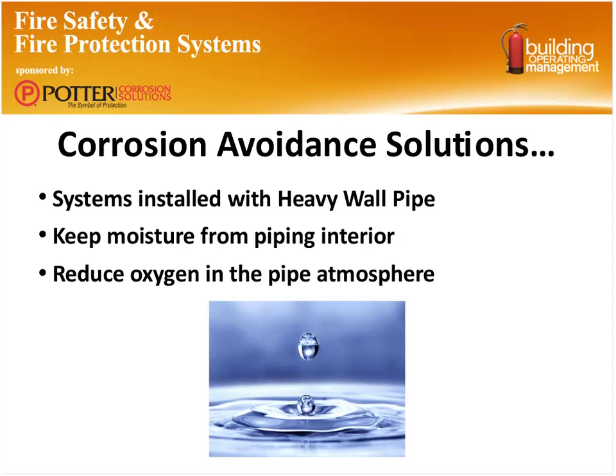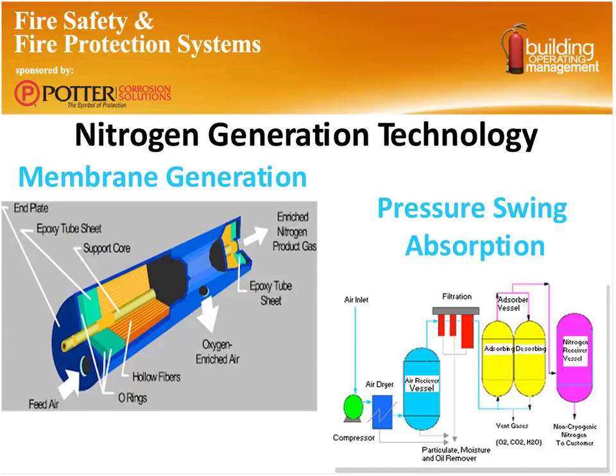So how do we reduce oxygen in the pipe atmosphere? Well, there's a couple of different technologies, but the most prevalent one today is working with a nitrogen injection system. We've had some very small systems where we used traditional bottled nitrogen with a regulator system to inject nitrogen in place of compressed air. But those are not very cost effective on a bigger system. Every sprinkler system that's dry or pre-action has a few leaks. Air leaks out, has to be made up, and over time, it's difficult to keep up with the change out of typical compressed air bottles.